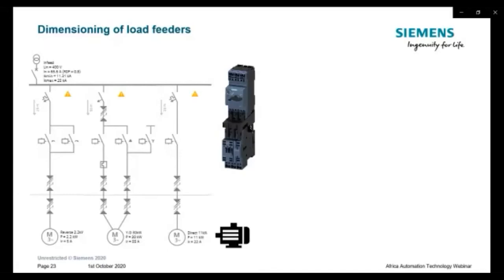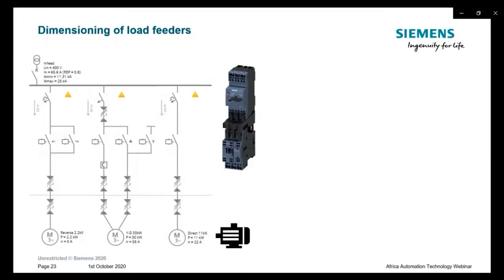So you need to have the requirements for general operating conditions such as voltage rating, frequency, current ratings, type of the distribution system, TN-S, TN-C network, IT network, besides application-specific requirements including load characteristics. Tripping classes shall also be considered during the engineering phase. Once those general operating conditions are available, you can go for the right load feeder dimensioning, whether you talk about a direct load, a reverse starter load, or star delta starter load.